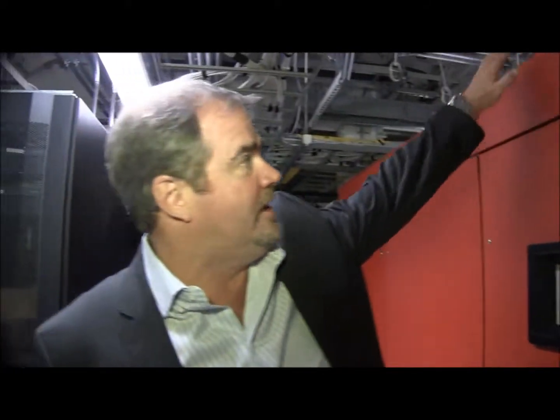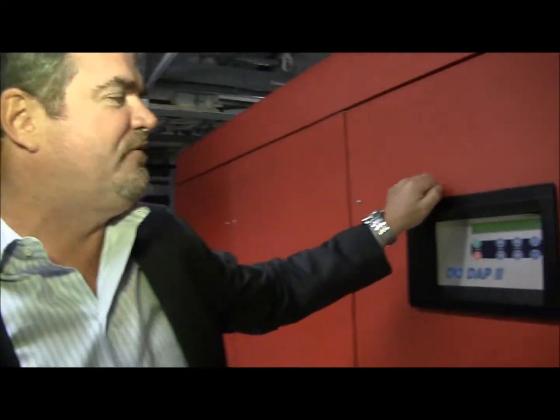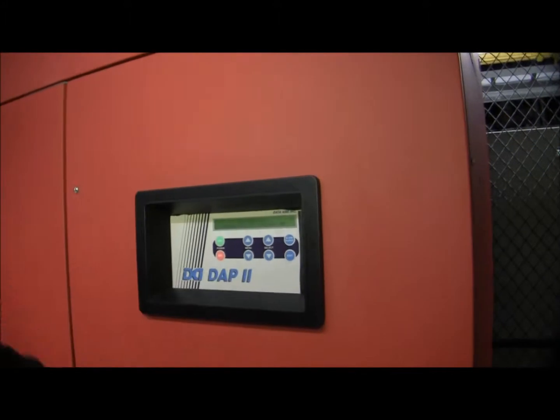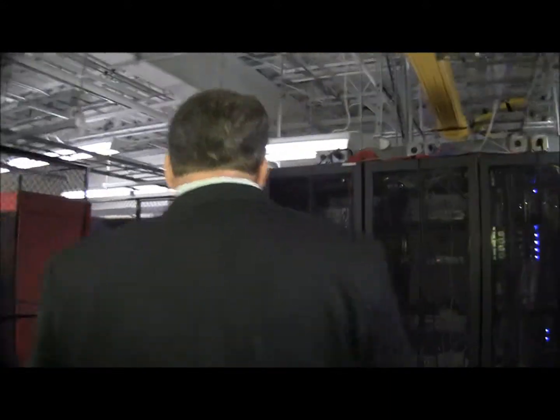The cooling utilizes 2-stage cooling. Right now it's telling us our input temperature is 73 degrees. Our output is 46. And though you can't feel the temperature, Brady can tell you later, if we walk in a cold row, it's in the low 60s at the entrance point. It's a standard cold row environment with the cold tiles on it. Cold air comes in, hot air releases and cycles back through the CRAC units. This floor currently is running an ambient draw of 281 watts a foot for our customers. We have some very large customers that utilize up to 23 kilowatts per rack. There's some Rackable systems in here that run on DC power that are actually quite large, 52U, and they draw a lot of power.